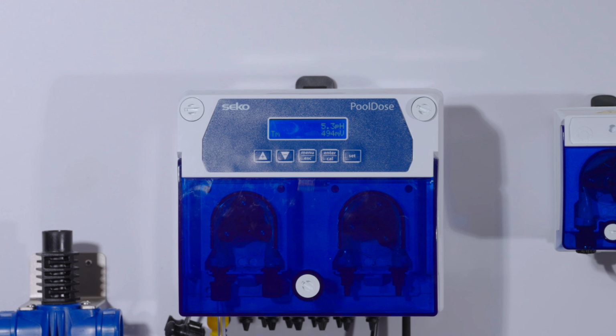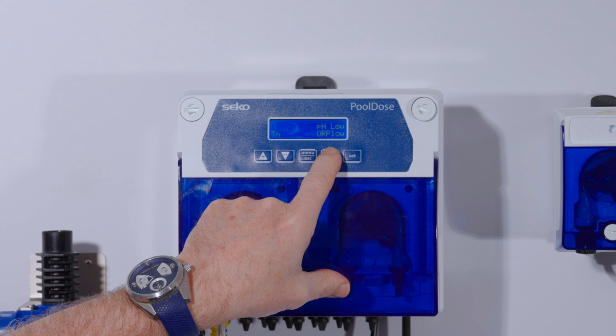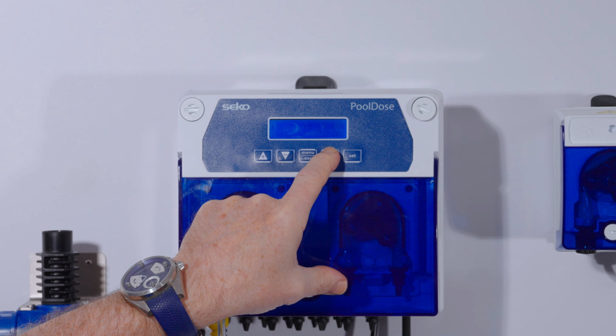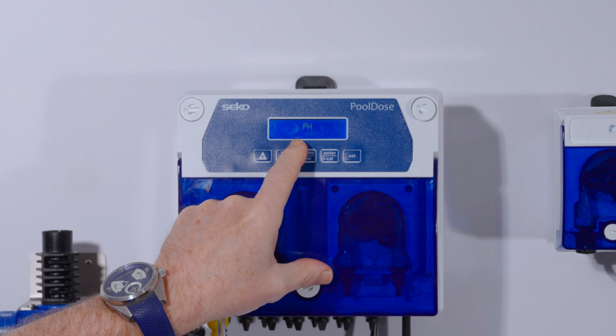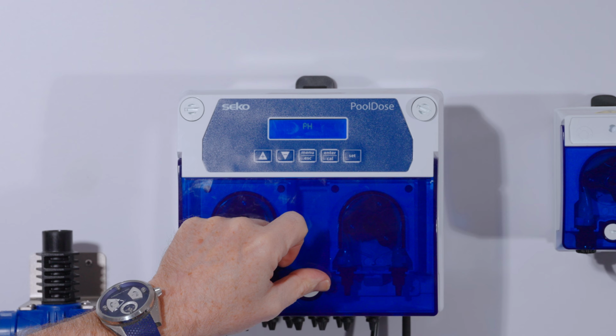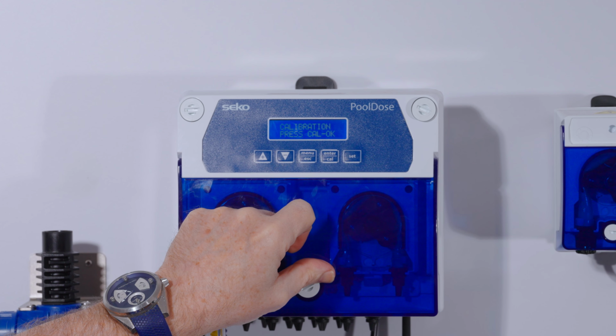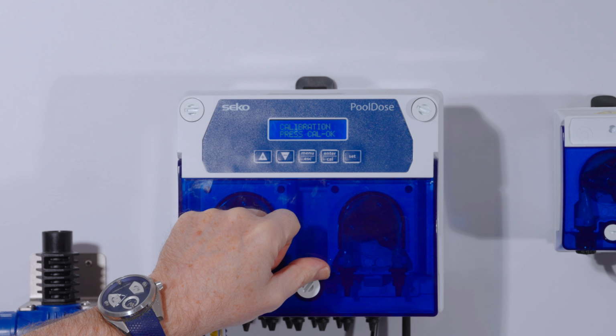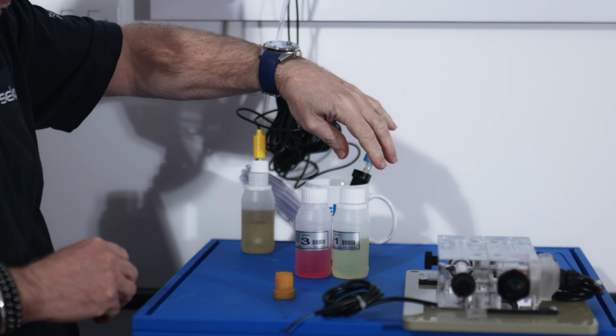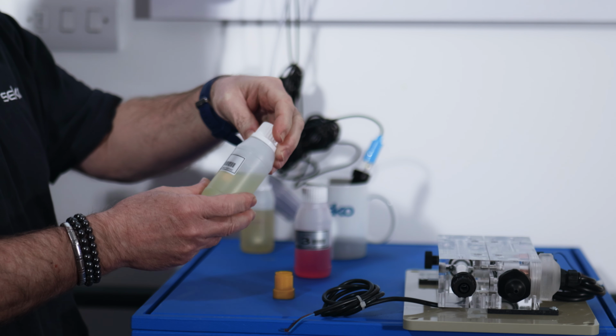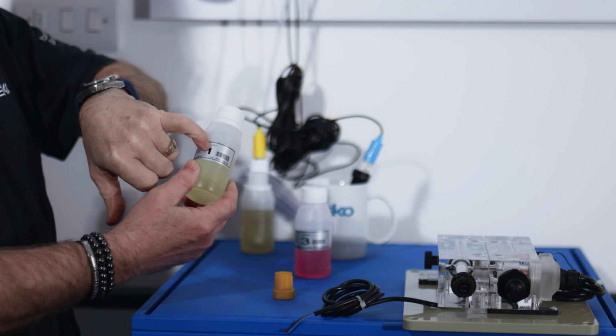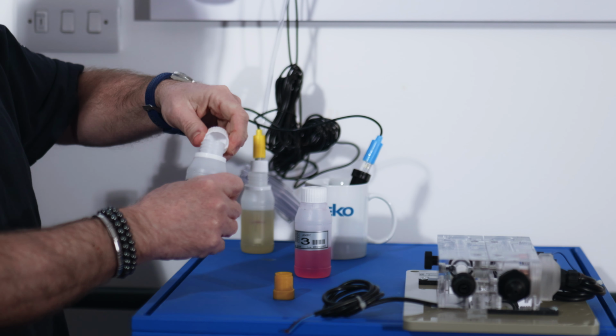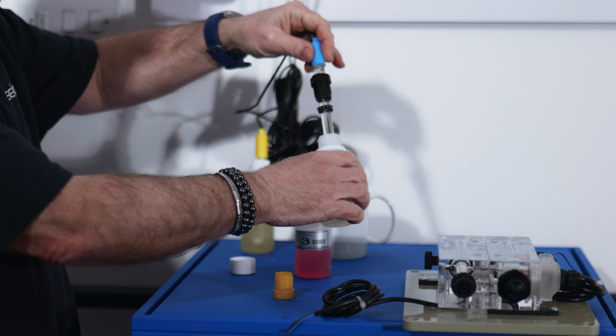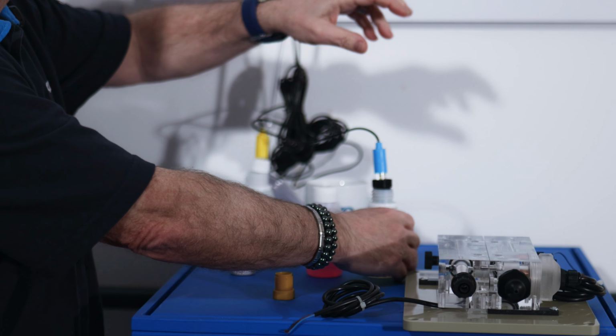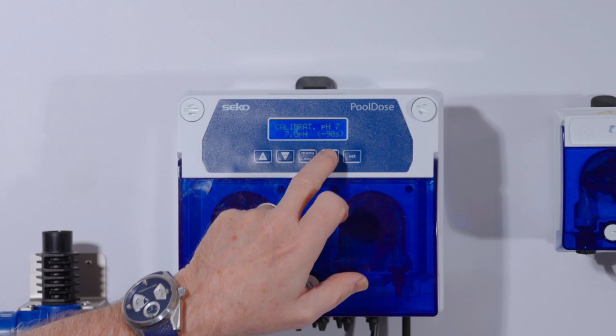So the calibration process. If we press and hold the cal button, we'll go into the calibration menu and we can see that pH is flashing. If we enter this, we'll get a request to see if the calibration is okay. At this point, we should use the buffer solution supplied. Please take note of the pH of the relevant solution. We can place the probe in the solution and we now press enter.